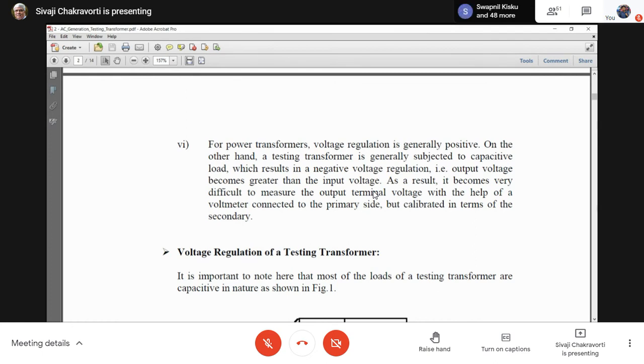This is the first important point. And the second point is, I should have an idea what the voltage regulation is, and then I should apply a relatively lower voltage at the transformer end so that the terminal voltage remains 28 kV. Now, let me tell you one thing. In my high voltage lab, there are technical staff, and they know how to use this transformer probably better than me because they are doing it every day. So how to apply the voltage, how to connect it, they know. And they also know that if I have to apply 28 kV at the terminal, probably we have to generate 26 kV. Then the terminal voltage will be 28 kV.